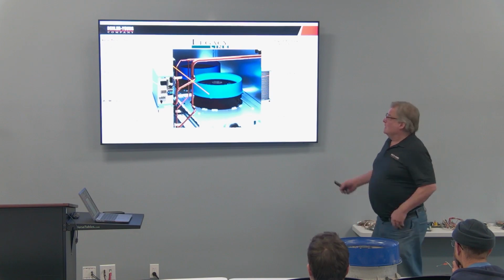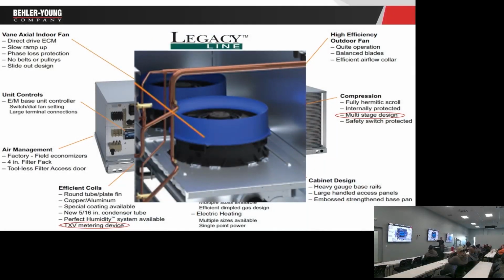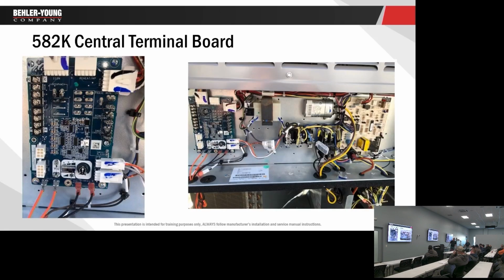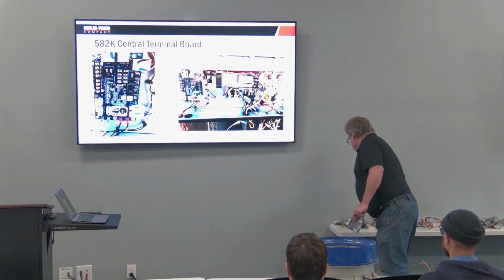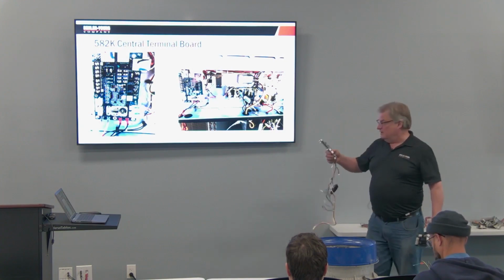Okay. So when you have the dual fans, it has it, and when you have the single fan on the bigger 7.5 ton, it will have it. So if you walk up on a unit, it's not doing anything, just sitting there off, no 24 volts on R and C, it may be one of those blower motors. Okay. So, the central terminal board. Okay. Now, the old 580 for the last 20 years.